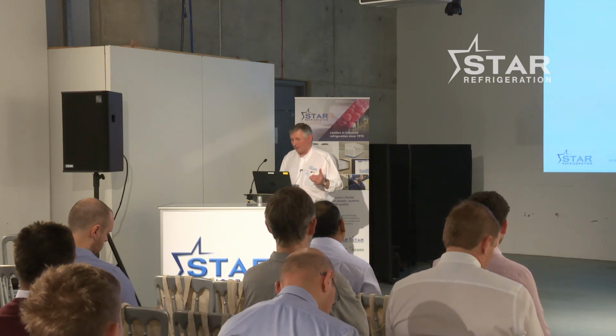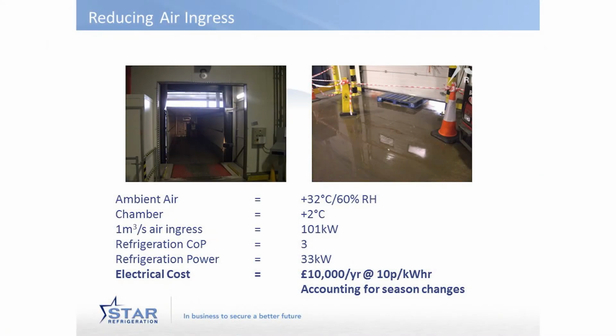It's really quite incredible. So the first one, eliminating cooling load. Well, there's a whole bunch of ways. I mean, maintenance comes into it. Willie will be talking about maintenance later, so I don't want to steal his thunder particularly. But if you're running a cold storage operation, ingress of air is a major source of additional loads on the refrigeration system. So you can see 2 photographs here.